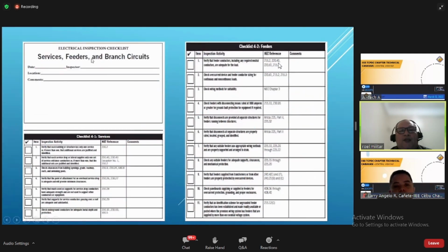Here we have this electrical inspection checklist, titled services, feeders, and branch circuits. You take the date, who conducted the inspection, the locations, and what the comments are. In the checklist, you simply check the items if applicable, where the referencer is the NEC references, but we can also make changes in terms of Philippine Electrical Code references, noting the particular sections in the code and what the comments will be. Not all of these items will be applicable during the actual testing. That covers services, feeders, and branch circuits.